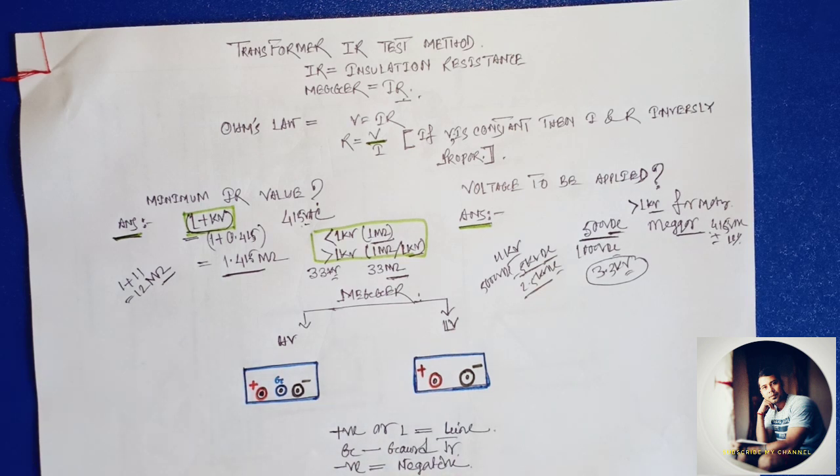Friends, in a high voltage system, in high voltage cables, insulators, transformers, in these high voltage sections, surface leakage current should be considered while taking the IR value, because it can change the actual IR value result we want. So it is good practice to connect the surface and the rest of the windings that you are not going to test to the G terminal. In practical, when we watch the next page, we will come to know where to connect it.